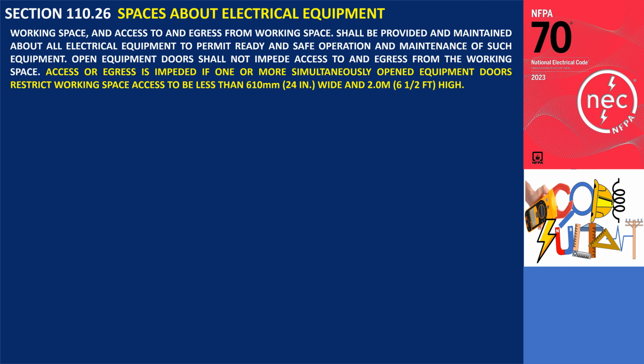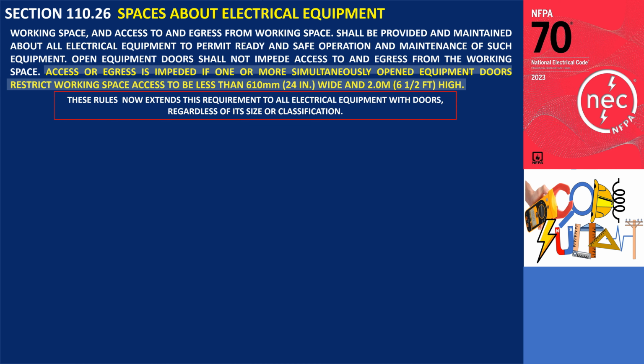It is crucial to consider that if the access to the working space is restricted to less than 610 millimeters or 24 inches wide and 2 meters or 6.5 feet high due to one or more simultaneously opened equipment doors, it is considered as impeded access or egress. These rules now extend this requirement to all electrical equipment with doors, regardless of its size or classification, as mentioned in the opening paragraph of this section.